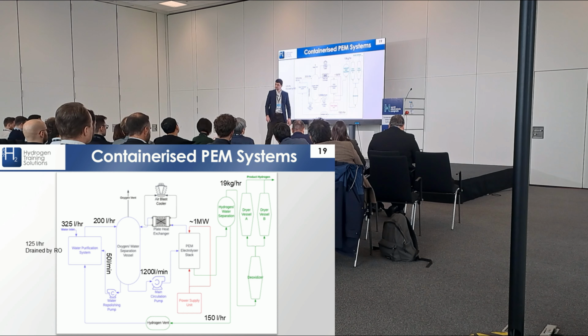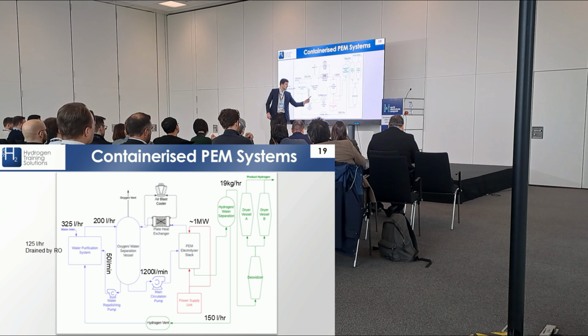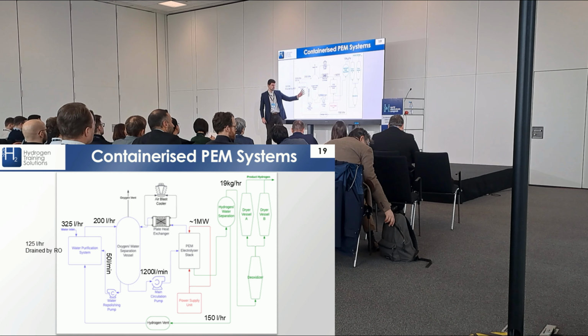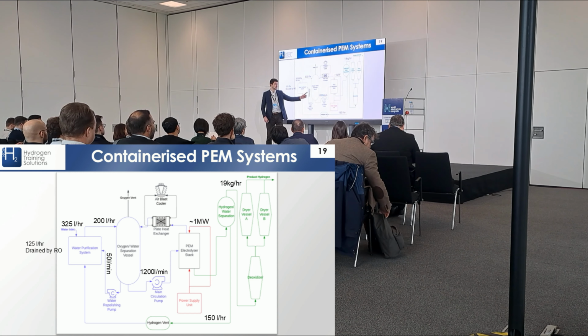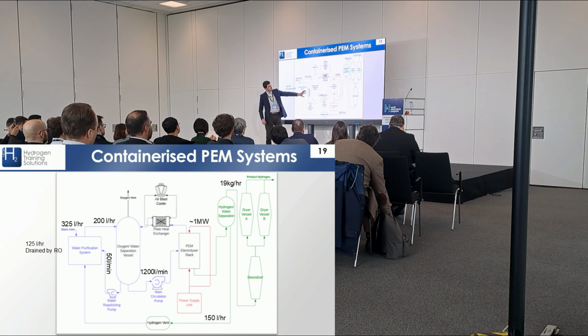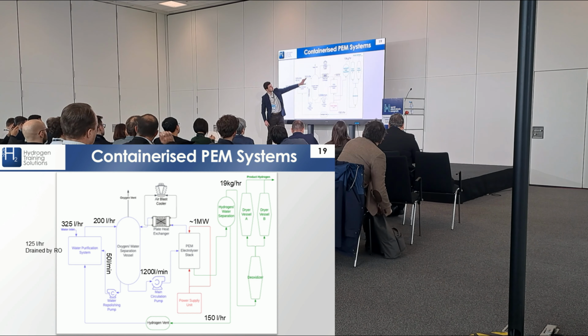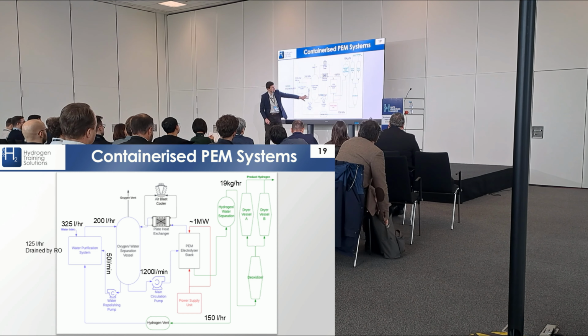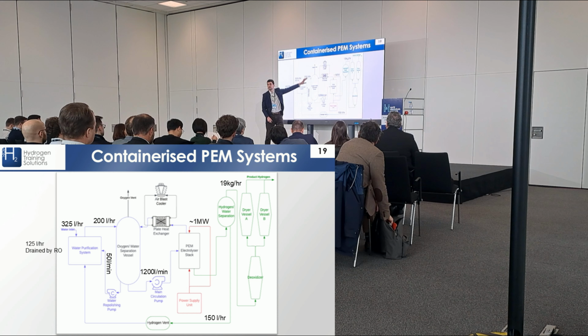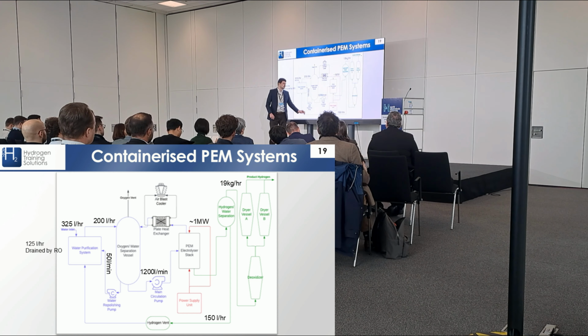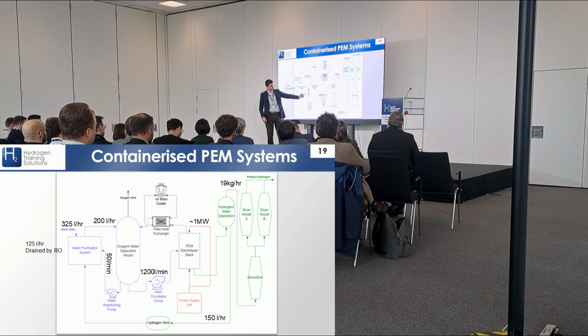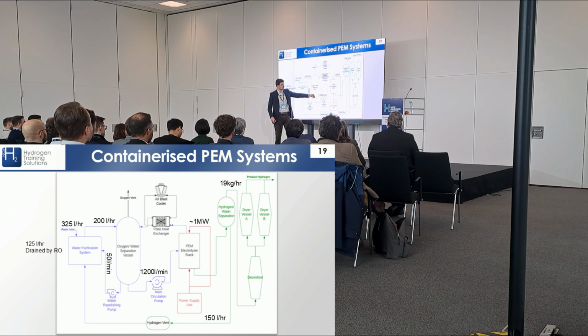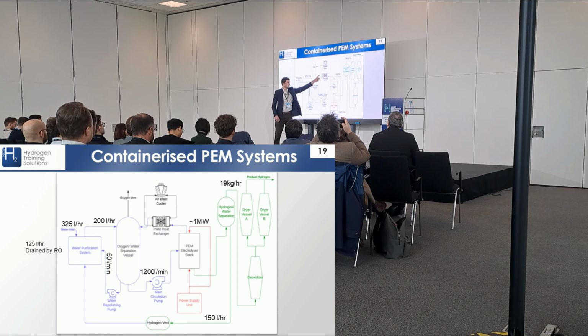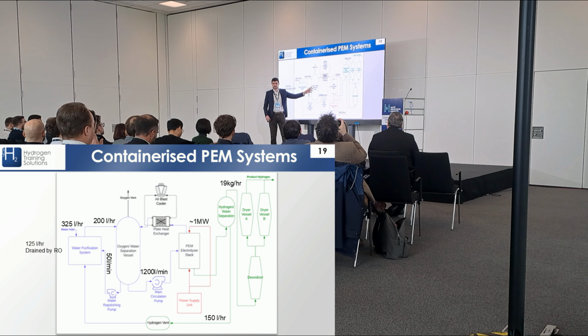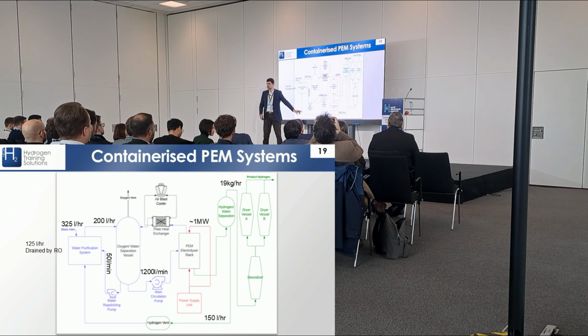So we have a water repolishing pump, and a water repolishing loop which pumps about 50 liters a minute back into the system - an extra loop here. That 50 liters per minute figure comes from taking approximately 1 to 5% of the amount circulating through your stack every minute, which you also repolish in the repolishing loop.